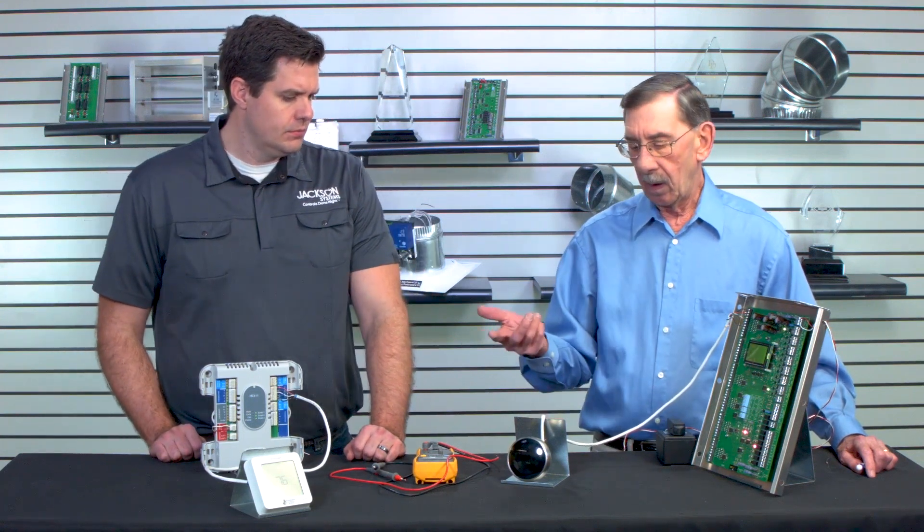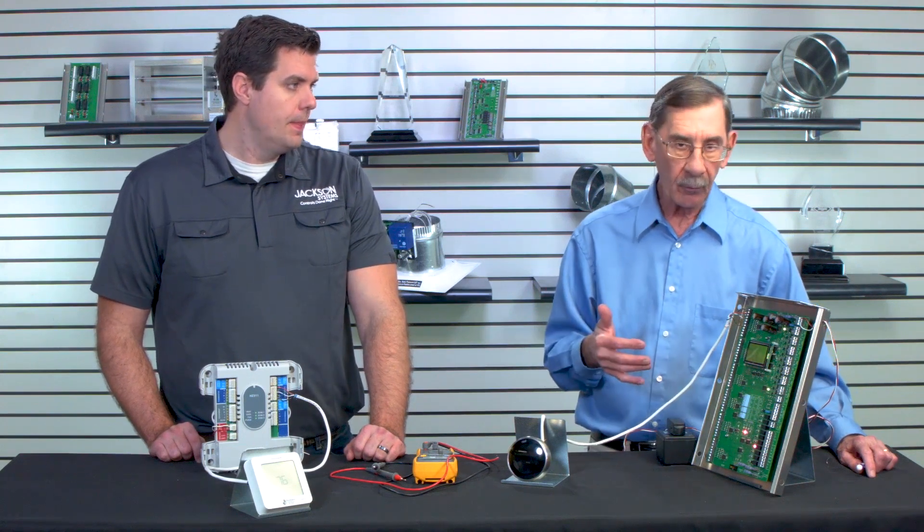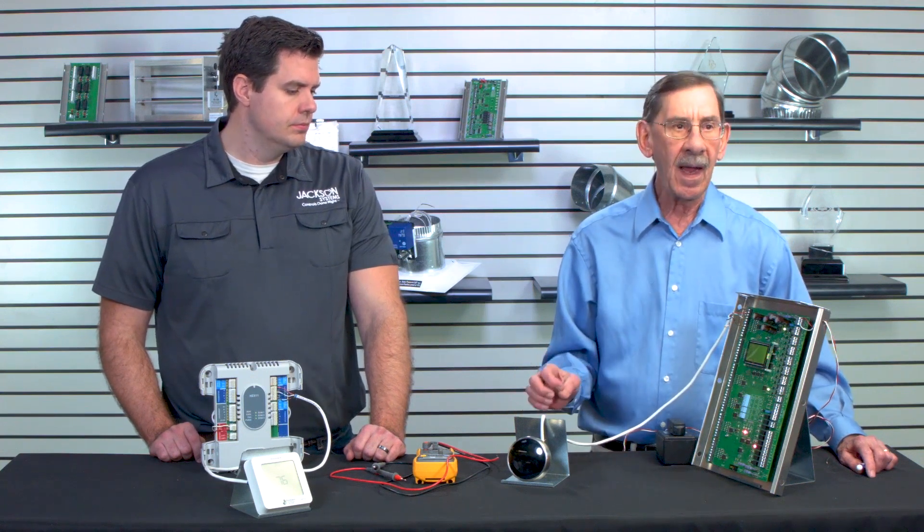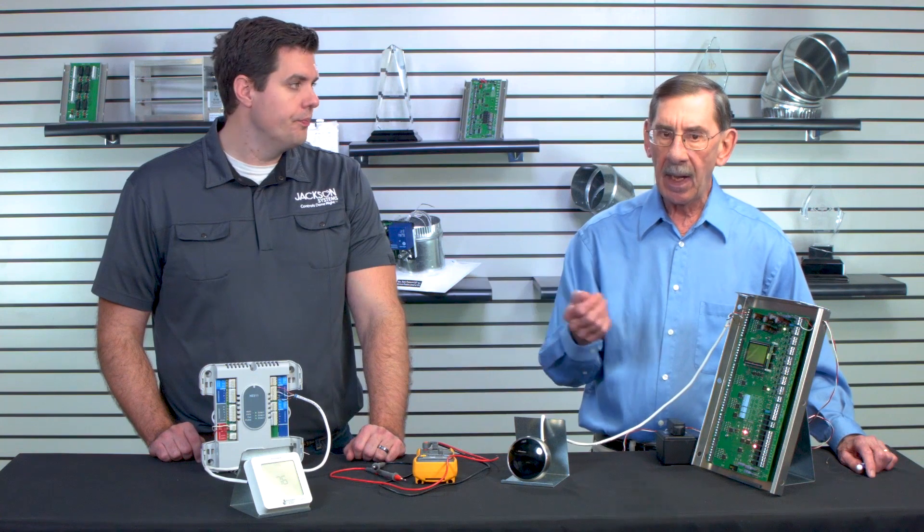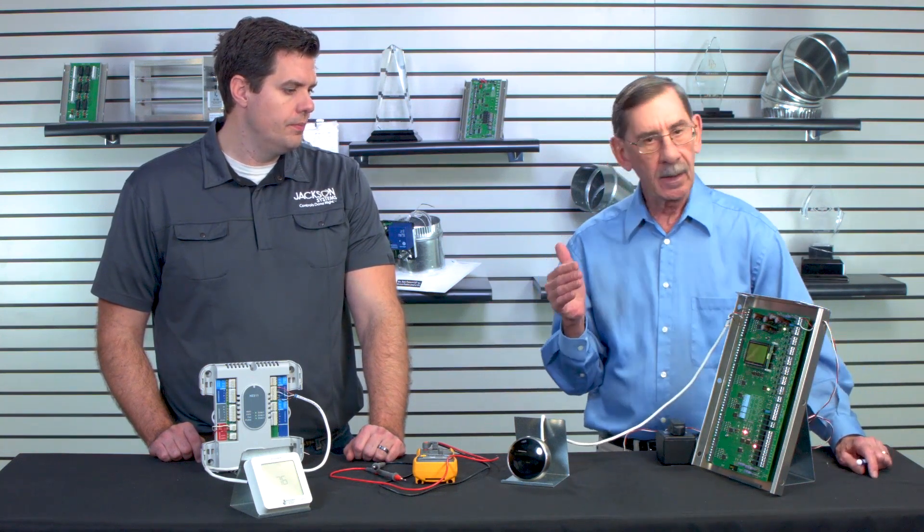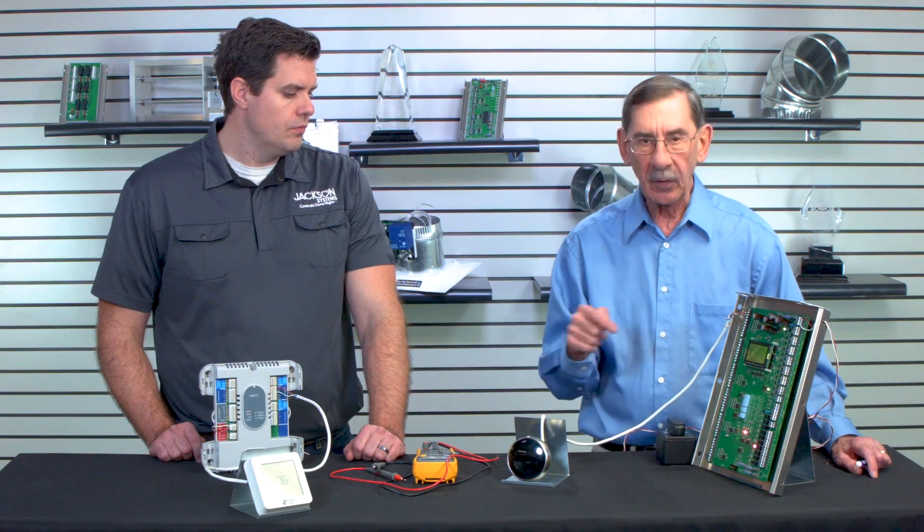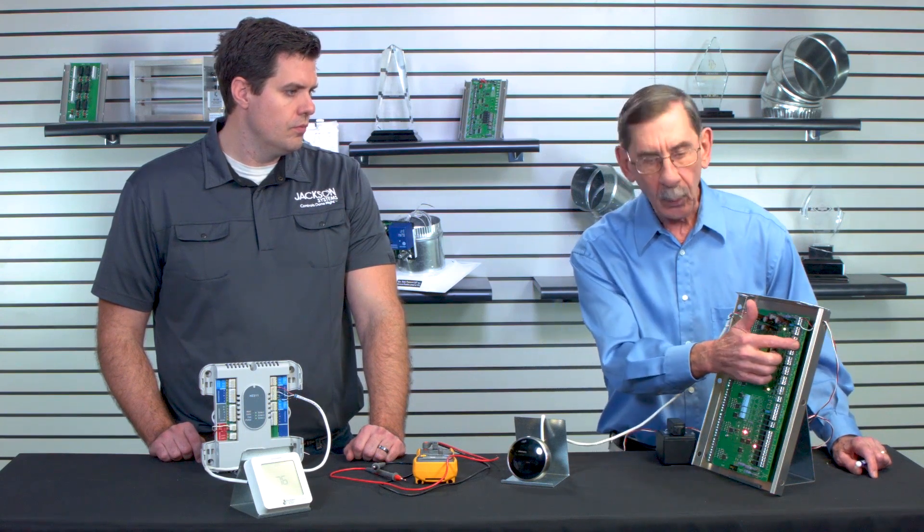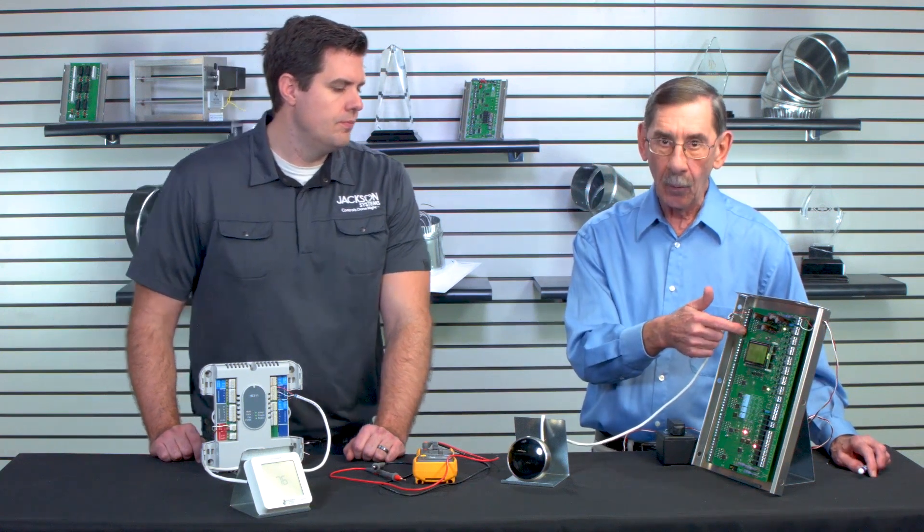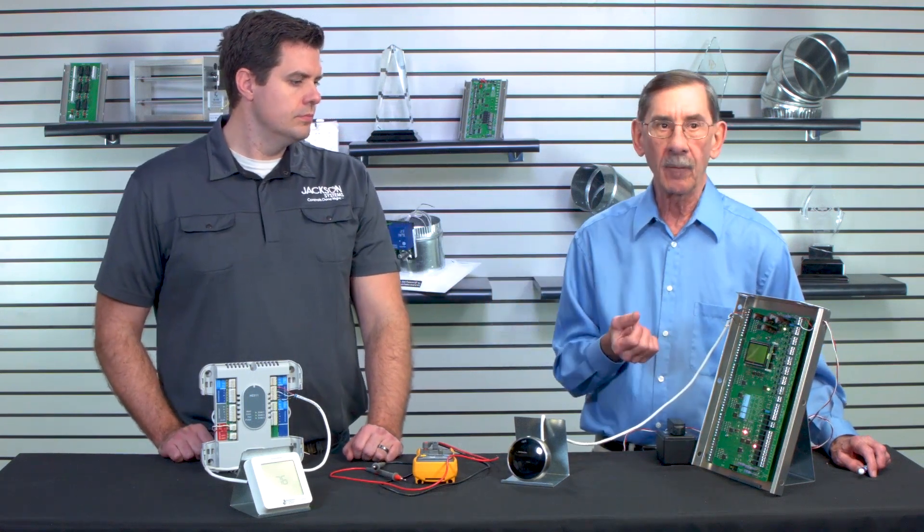Running wire. We're not talking about one thermostat going to the equipment anymore. We're talking about multiple thermostats, three, four, six. It's important that you tag your wires. You're running everything back to these panels. It's called home run wiring. And I really need to be assured that if this is zone one thermostat, that the output to the zone damper is the damper that is serving that zone.